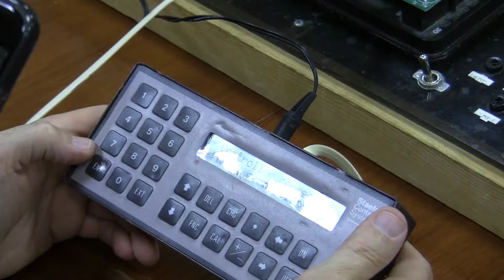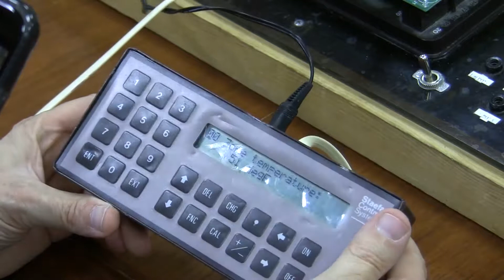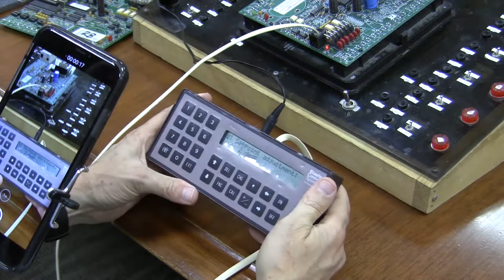The next thing I can look at is if I go to input 1, this is generally where you're going to see the set point offset. Okay, but in this particular case, since it's just this card on the table, it's not there. So I'm connecting again, and here I am. I'm looking at my zone temperature, right? And the next thing I care about, if I scroll down, is input number 1, which is the set point adjust knob. Okay, I care about that because I want to know, well, my zone temperature is this, but what's my set point? Well, is my set point 2?